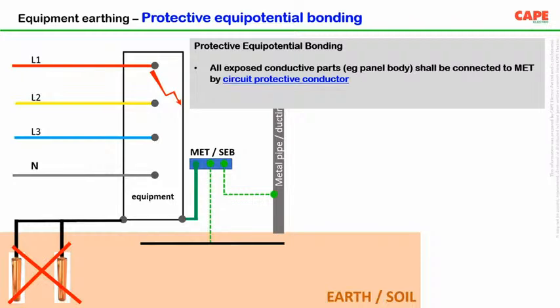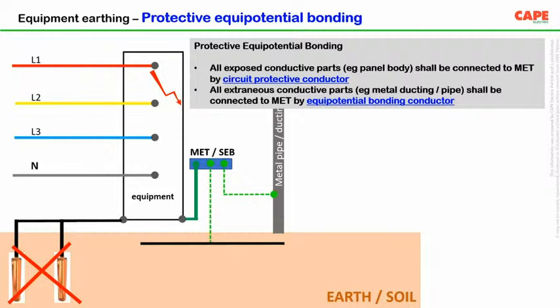There is no shock. But if the water is spilling over and creating another problem, this is not a recommended situation. You should keep it in such a way that accidental splashes of water are not going into the electrical system. Otherwise, if you have a perfect equipotential bonding, the chance of shock is gone. You are safe. Yeah, actually, the one point to be emphasized over here is that this must also be equipotential bonding.